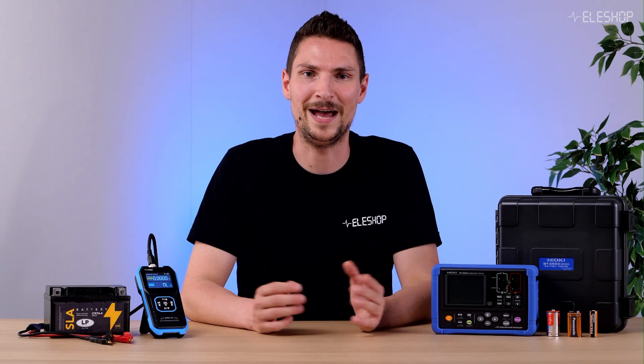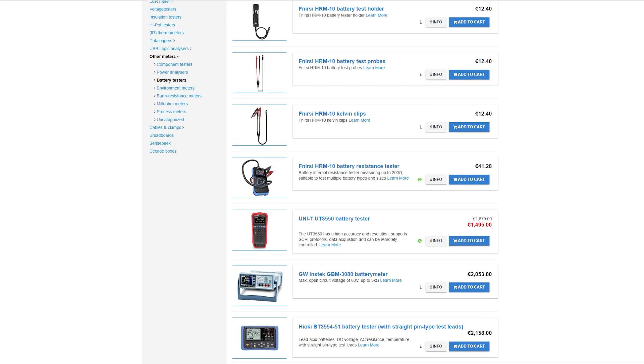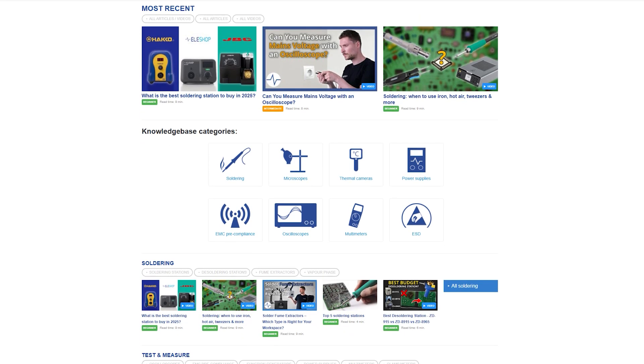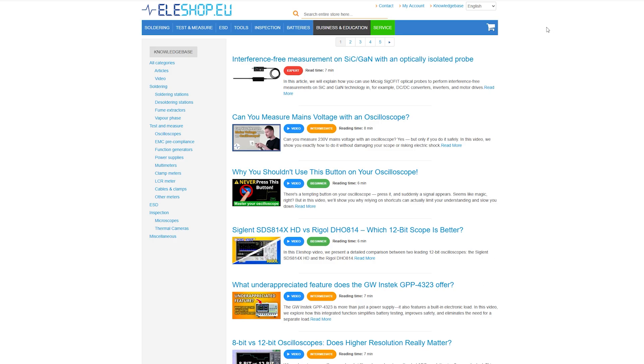In conclusion, a regular multimeter simply won't give you accurate results, but a battery tester which uses a 1 kHz AC signal with 4-wire clamps will. We offer a wide range of battery impedance testers in our webshop, for both small businesses and industrial applications. Let us know in the comments — do you already measure your batteries, and if so, which tester do you use? Want to learn more? Visit the Eleshop knowledgebase, where you'll find detailed articles and videos on testing and measuring.